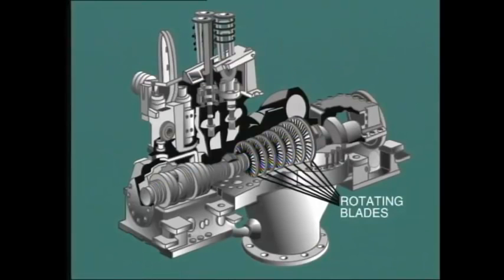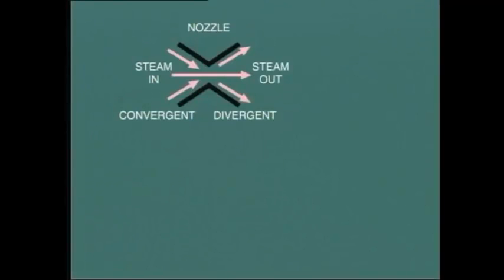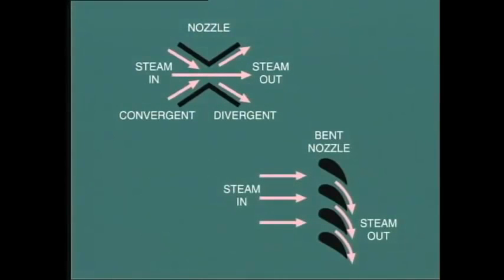And do not forget the stationary blade is always ahead of the moving blade. Actually, each pair of stationary blades is shaped to form a convergent divergent nozzle. However, the form of the nozzle is bent to receive the steam exiting from the previous moving stage and then to turn and redirect the steam onto the next moving stage. Now, before you raise the question, but what about impulse and reaction type blading? Let me say that in practice, when you're operating a turbine, it's not vitally important whether the blading is impulse or reaction. This is really a design and construction feature. However, it will certainly be worth our while to take a look at this subject, as the type of blading used does affect other structural features.